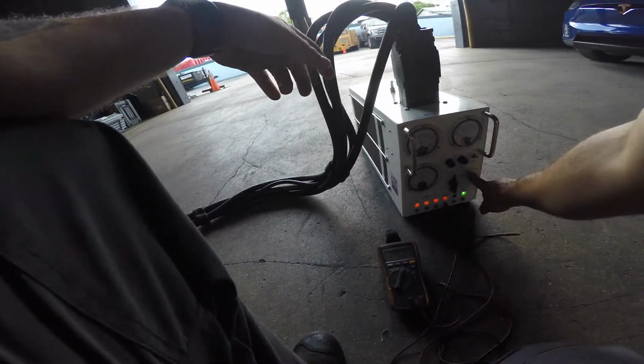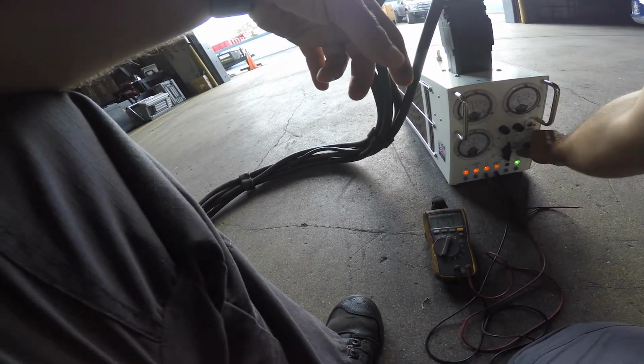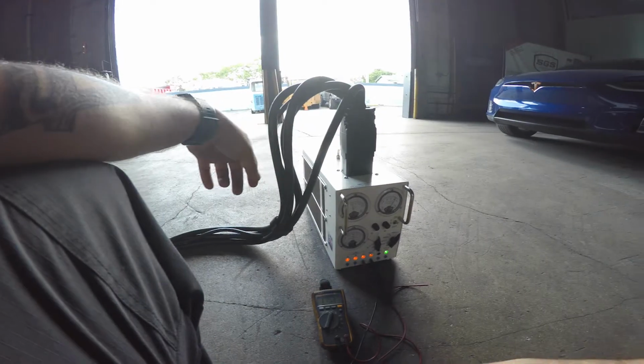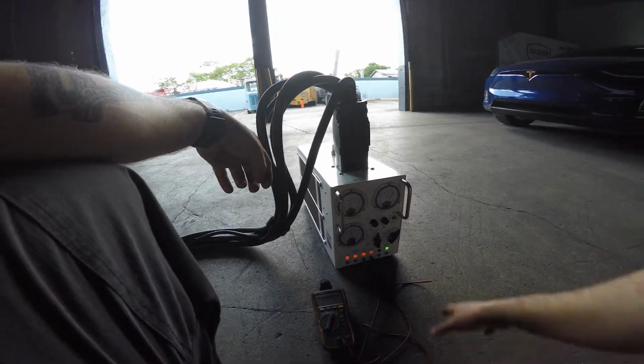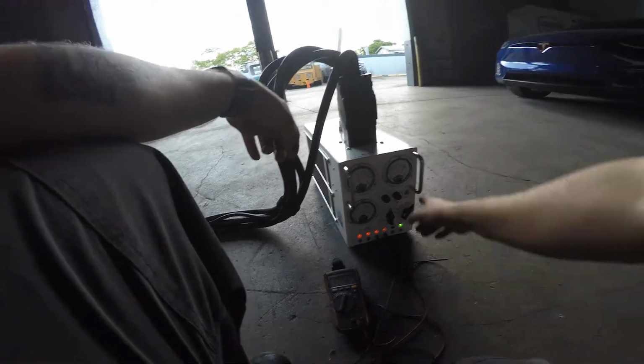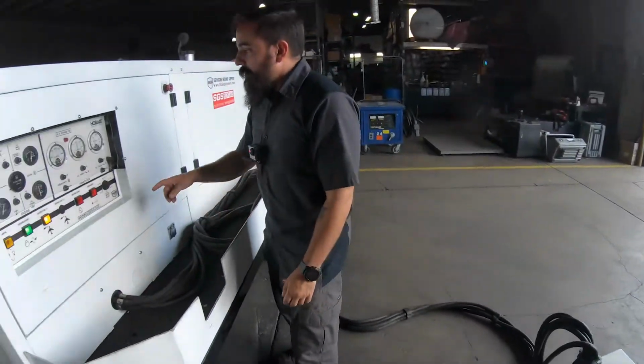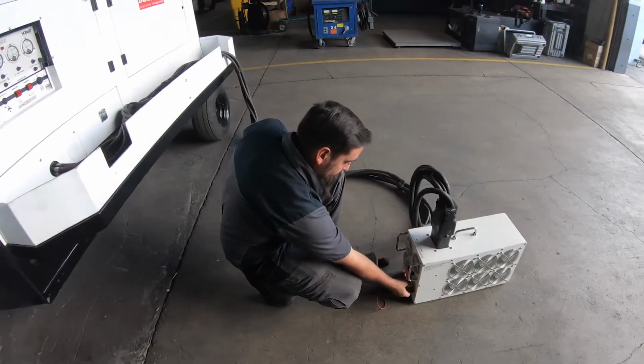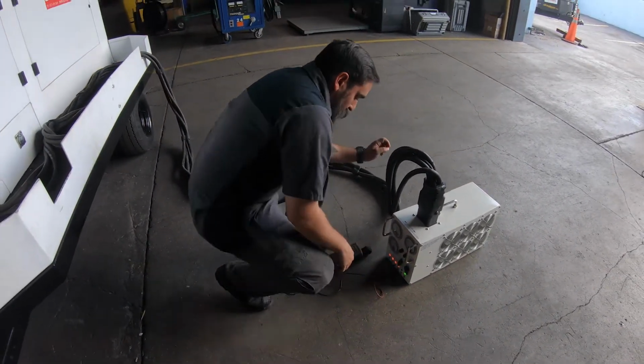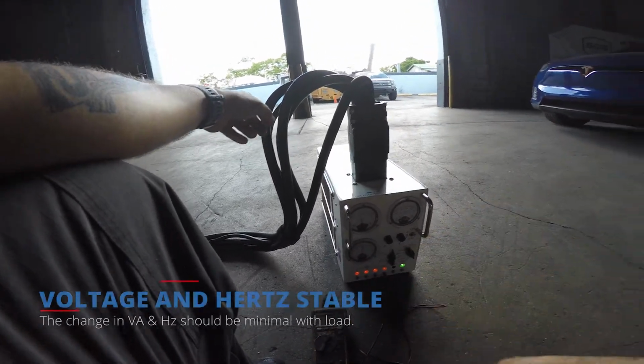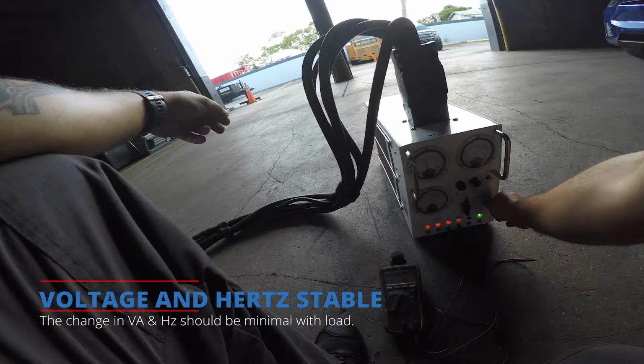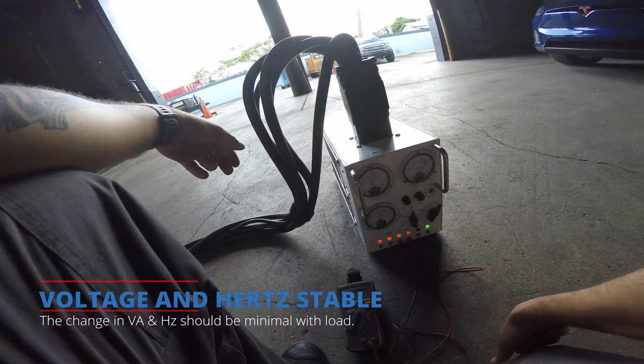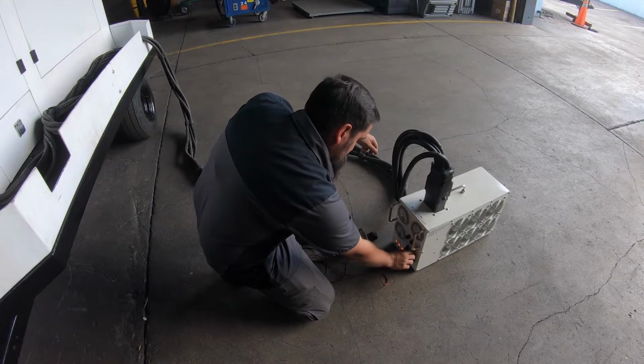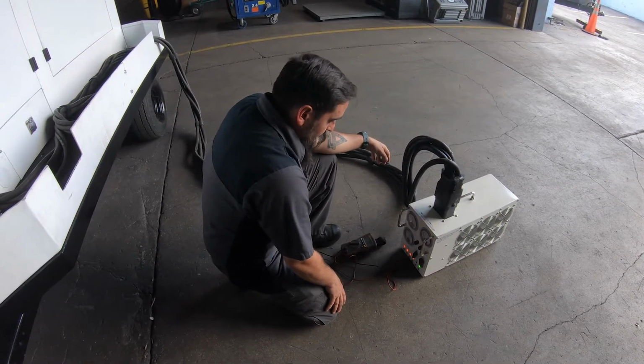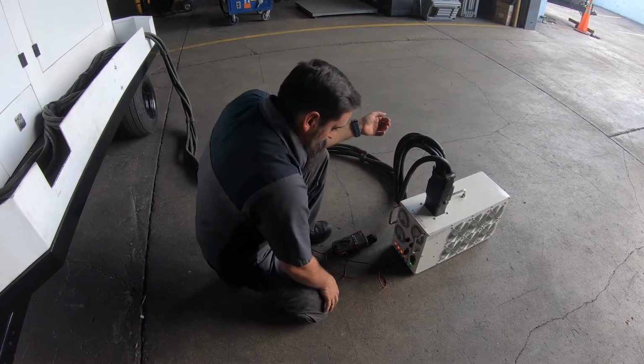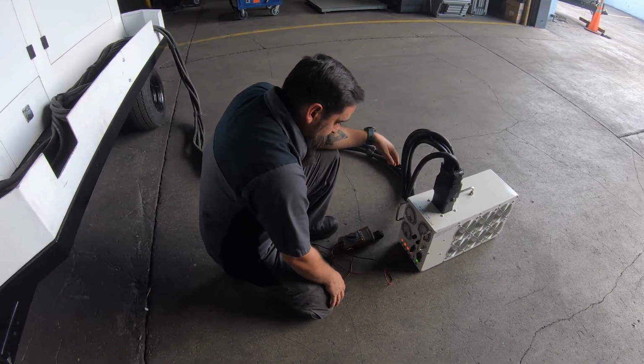Alright, so to apply load, you just apply as much load as you want. In this case we're gonna go full load, which is what this unit is made for. It should give you around 200 amps on here and on here. That's it. We're gonna bring it back down. So what you're looking for is that the hertz stays stable, voltage stays stable. Test it out for a couple minutes, make sure it can hold the load, that the engine's not dropping.